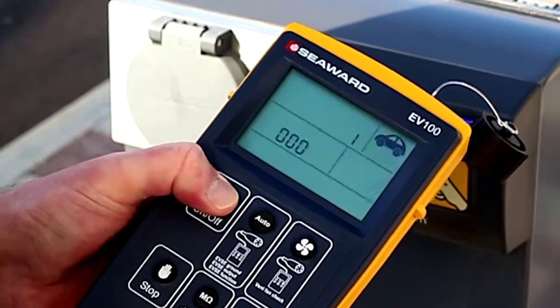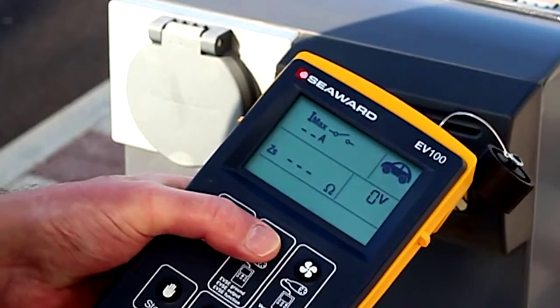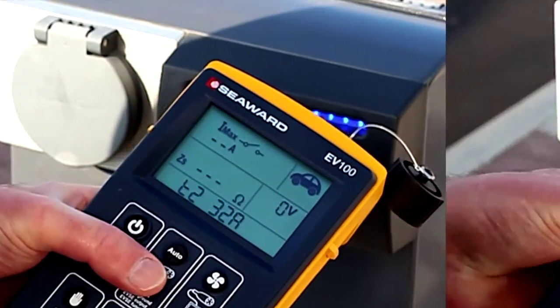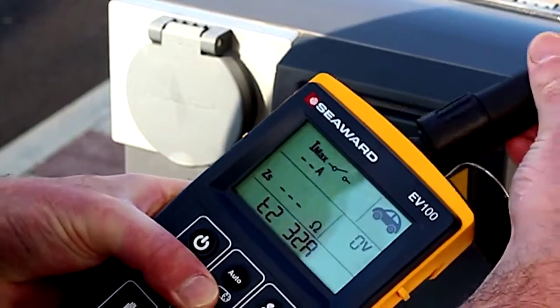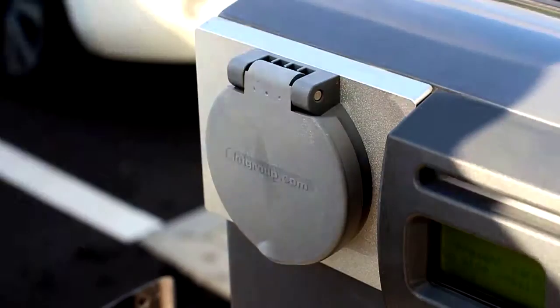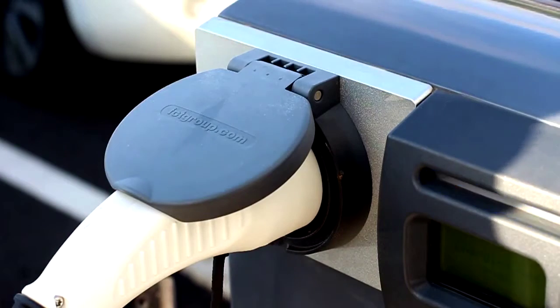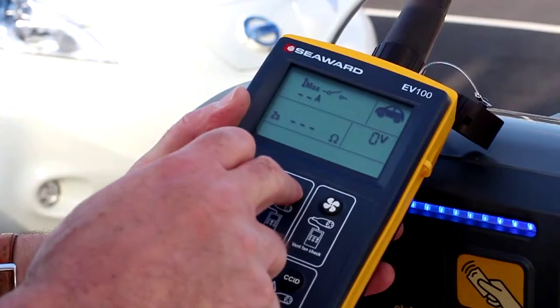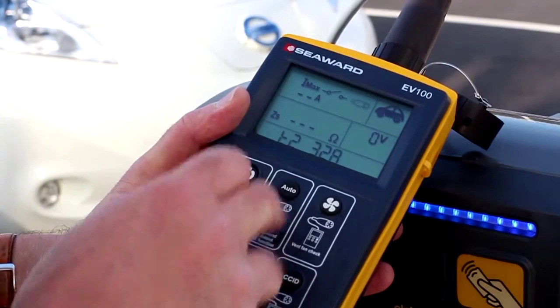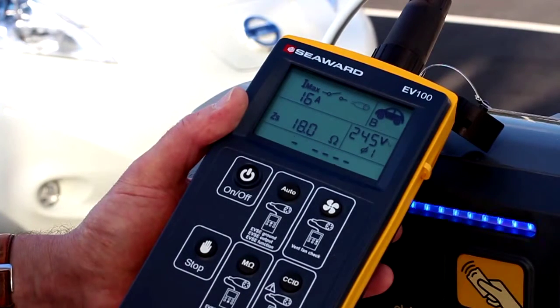To perform the extended auto-sequence, which includes simulated diode faults, press the on-off key to turn on the unit. Using the auto-key, select the type of cable you would like to simulate from the list. Connect the required test adapter to the EV tester. Then connect the EVSE to the EV tester using the test adapter. Press and hold the auto-key until the EV tester beeps to select the extended auto-sequence. The EV tester will now run through the auto-sequence.